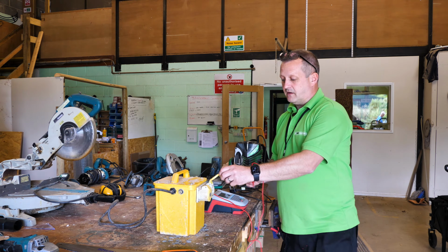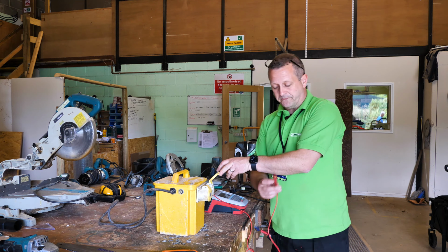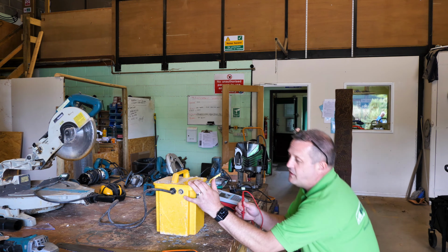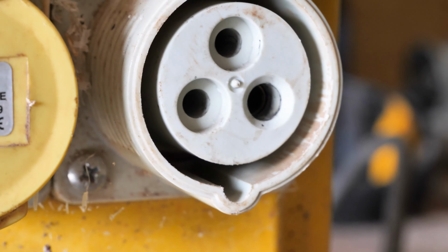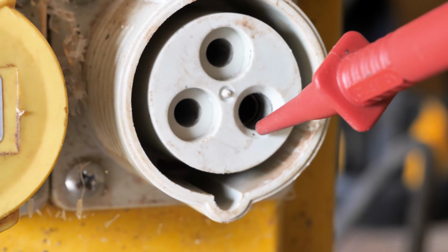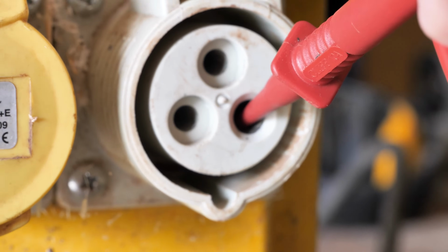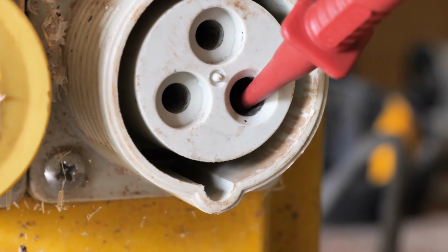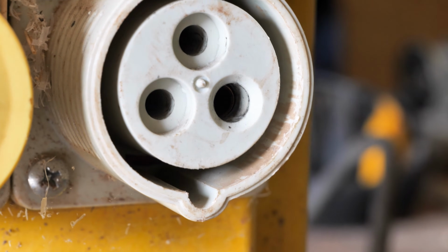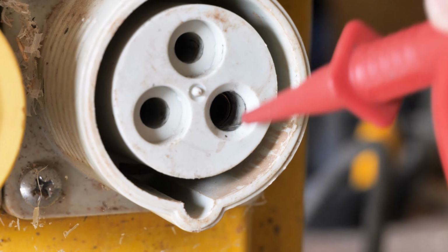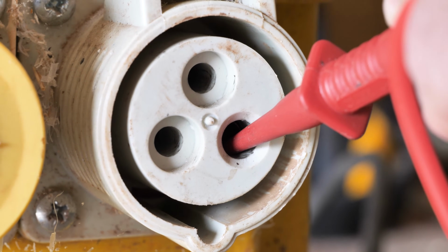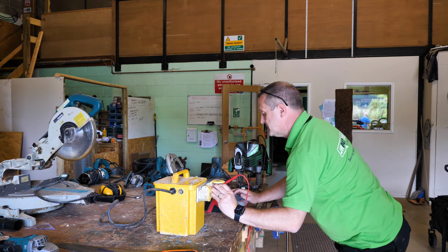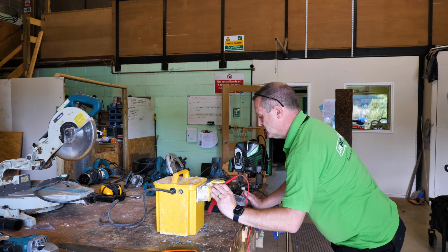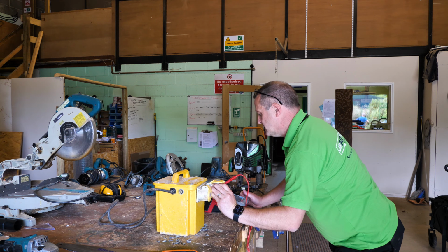class 1 test. Now what I found is to use the probe rather than a crocodile clip, and using the earth part of the connector, you'll notice that one is slightly wider than the other two, and that is your earth probe. So all I do is get the probe, and you can just see inside there is a copper sheath, and all I do is slide the probe down until it makes contact with that copper, and just hold it there whilst doing the actual test. So then let it go and do its thing. And that's showing a really good earth reading of 0.01, doing the insulation resistance, and then it'll do a leakage test.